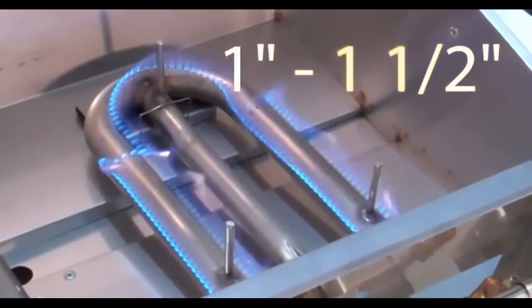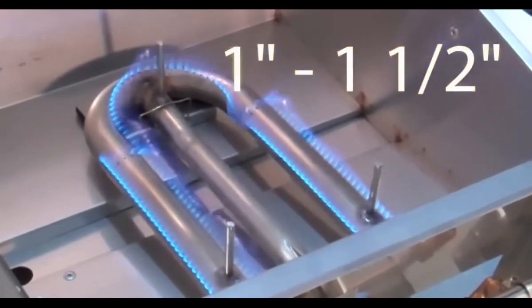Flames should be 1 inch to 1.5 inches tall, blue with yellow tips and touching the burner.